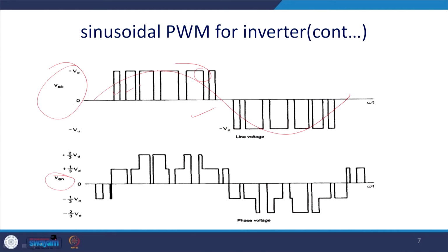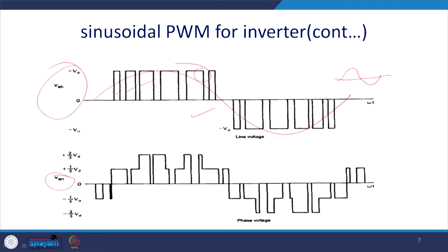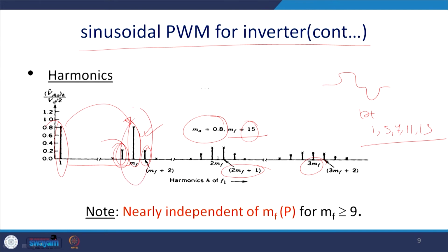But let us go back to this, the voltage waveform is sent through an inductor. If you are driving an AC drive, the winding has an inductance. For this reason the current will be sinusoidal. For the fundamental it will offer some amount of impedance, but for the Mth harmonic it will offer M times Z, thus the current will be reduced by M times, and thus the current THD will be lower in case of the PWM. That is the biggest advantage of this PWM.